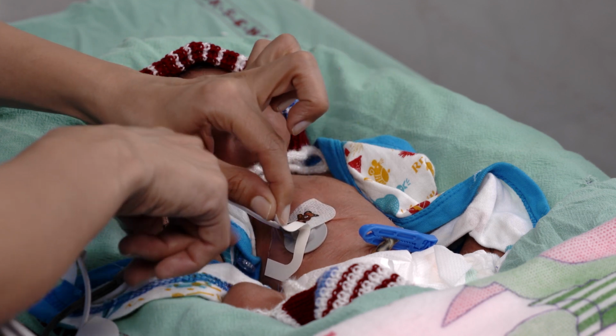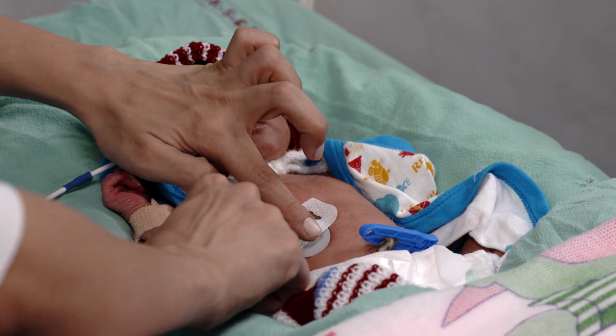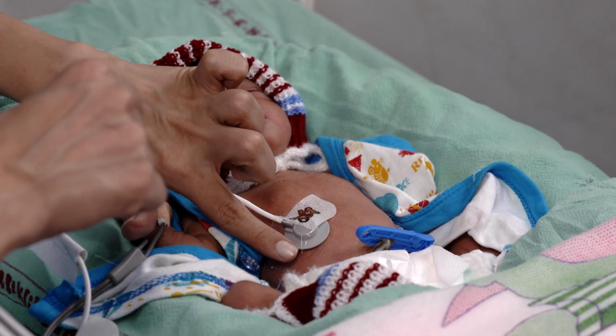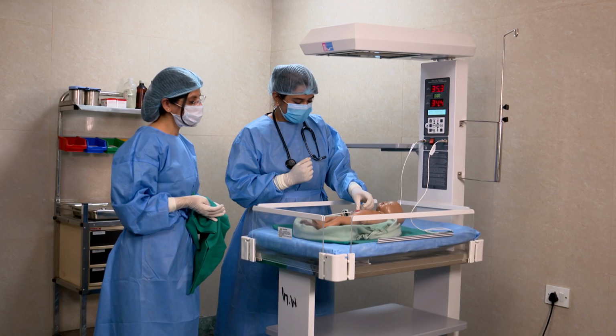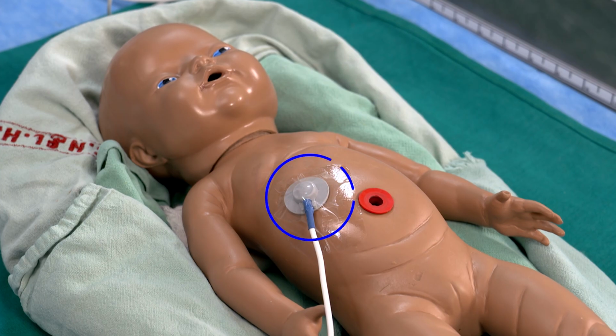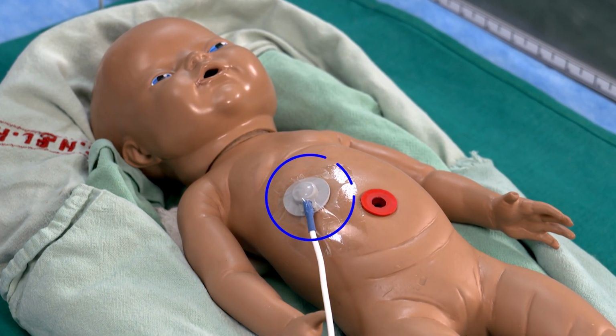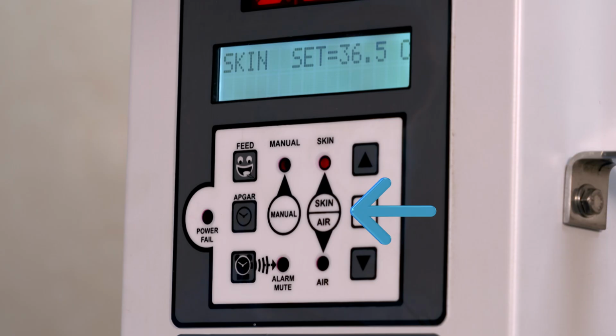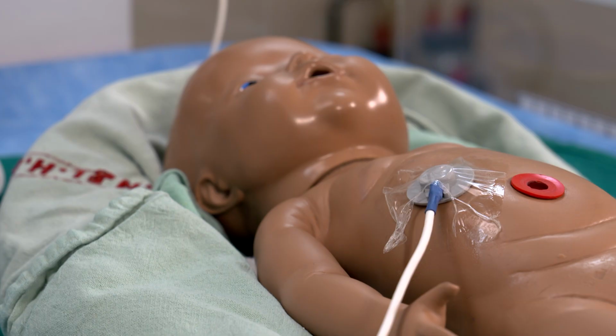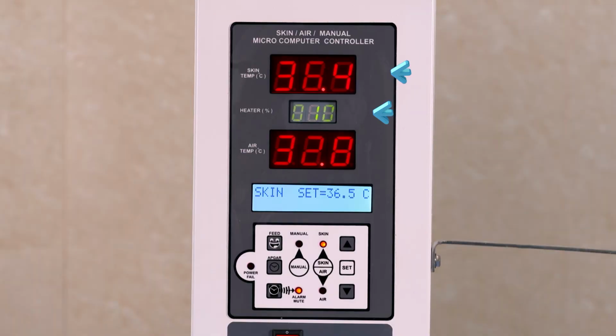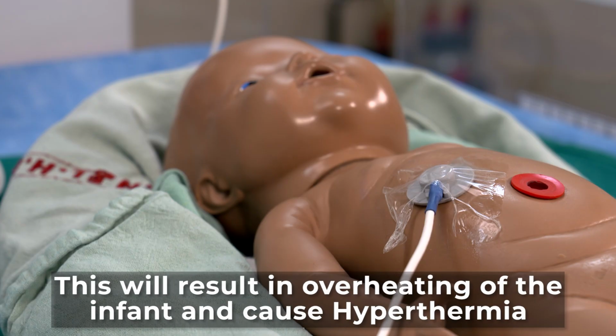Connect the skin probe to the baby's right upper quadrant of the abdomen with a skin-friendly adhesive. Make sure that the temperature probe is attached appropriately while using the warmer in the servo mode. If the probe becomes loose in the servo mode, then the measured temperature will fall and the radiant warmer will increase the heater output in response. This will result in overheating of the infant and cause hyperthermia.